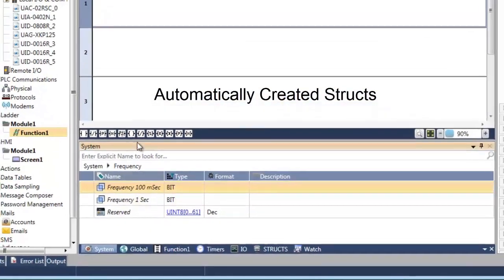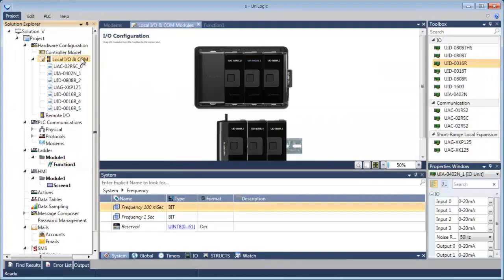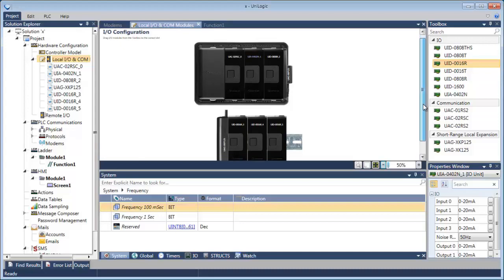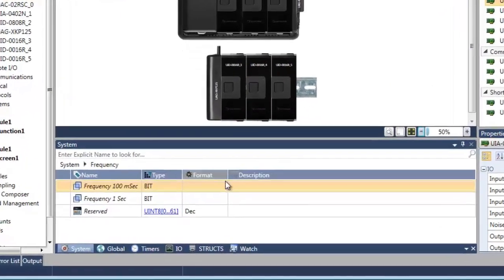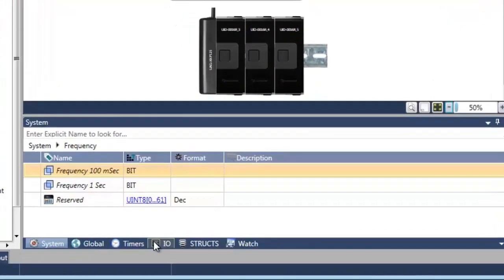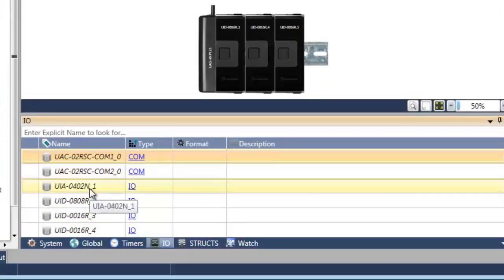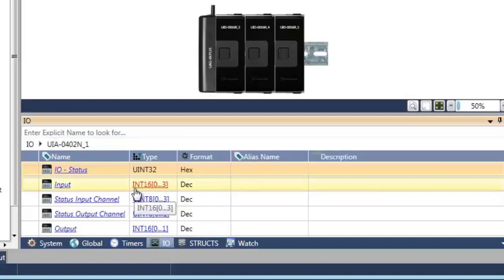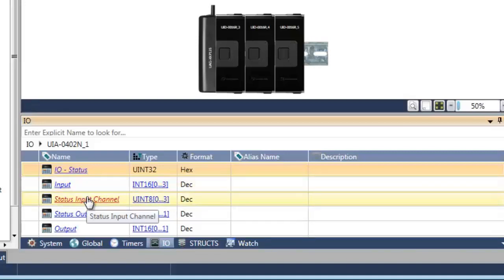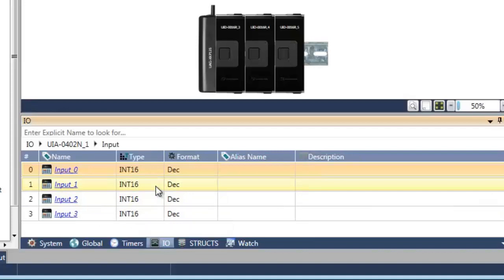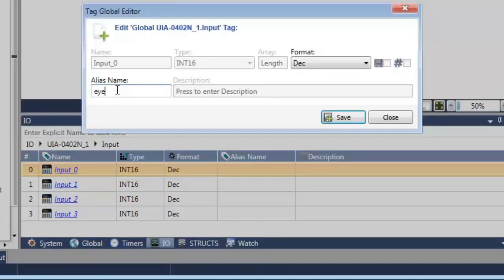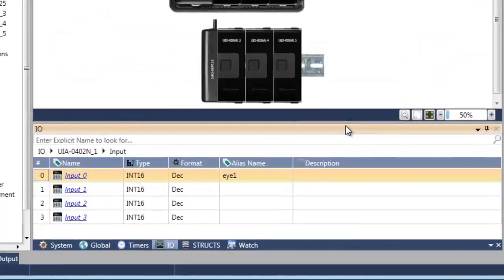Next, let's take a look at automatically created structs. These are created by UniLogic when you add elements to your application, for example during hardware configuration. Now you can see that we're going to click on IOs at the bottom of the screen, and we will see the COM modules that have been added to this application. Now we're going to take a look at one of the IO modules. Here you can see you've got status, the input values, and status for each channel. If we drill down, you can see that each input has its own separate data tags. You can assign aliases to these for ease in addressing later on.